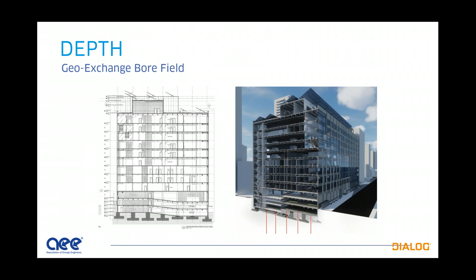So one of the issues with ground source or geo exchange systems is you need a balanced load. And for an office building, even in a cold climate like Toronto, we found that it's a cooling dominated building, so the loads aren't super balanced. Just as an anecdote, I live in Vancouver, I'm in the Vancouver studio, and we've had ground source heat pump systems here for quite a long time. Some of the first systems to go in the Vancouver area were at schools, in the early 90s or late 80s.